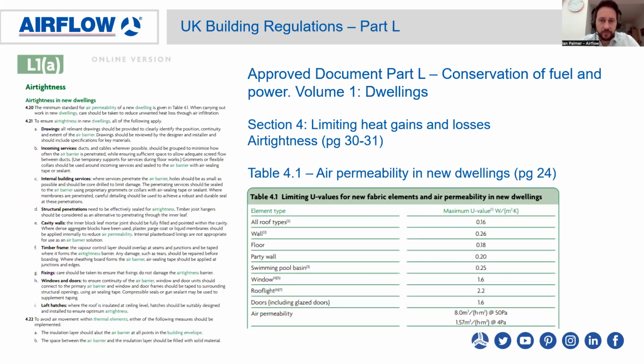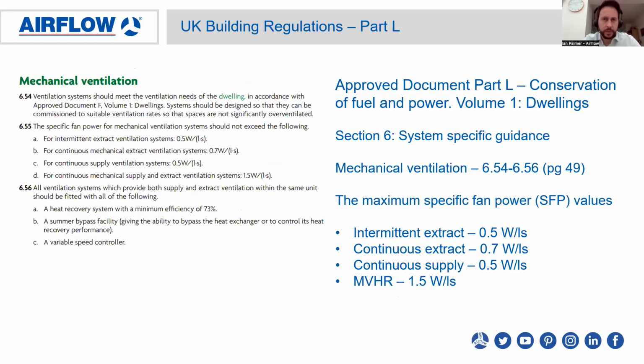So going to Section 4, limiting heat gains and losses and air tightness, and going straight to Table 4.1, this covers the air permeability in new dwellings. And then to Section 6, all about the system-specific guidance and focusing on mechanical ventilation. It details the maximum specific fan powers. So you'll see there the intermittent extract 0.5 watts per litres per second, continuous extract 0.7, continuous supply 0.5, and MVHR 1.5 watts per litres per second.